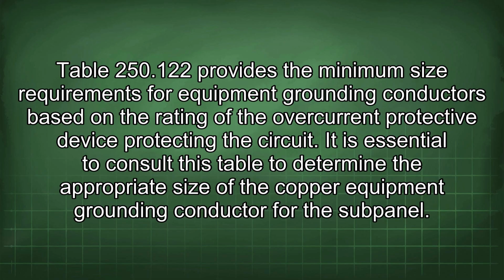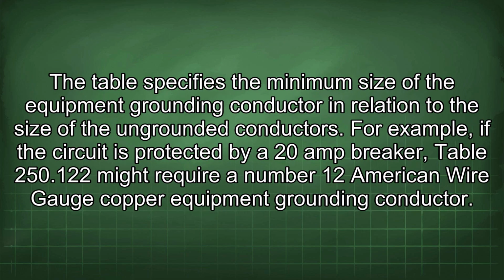Table 250.122 provides the minimum size requirements for equipment grounding conductors based on the rating of the overcurrent protective device protecting the circuit. It is essential to consult this table to determine the appropriate size of the copper equipment grounding conductor for the subpanel. The table specifies the minimum size of the equipment grounding conductor in relation to the size of the ungrounded conductors. For example, if the circuit is protected by a 20 amp breaker, Table 250.122 might require a number 12 American wire gauge copper equipment grounding conductor.